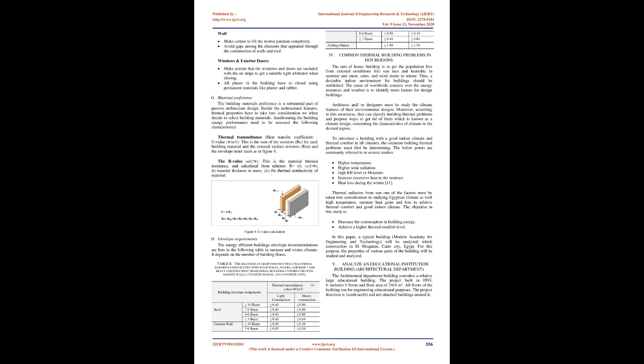Glazing specifications. Glazing thermal transmittance, which is comparable for roofs and walls: single glazing, U value equals 5.88 W/m2C; double glazing, U value equals 2.88 W/m2C. By adding argon to the air cavity, the U value can be lowered. To calculate the whole window thermal transmittance, the window frame must be taken into consideration. The G value indicates the energy transmission through the glass, as in figure 3. To increase daylight, the G value ought to be higher. However, to reduce glare in spaces with exceptionally strong external light, a decreased G value ought to be considered.